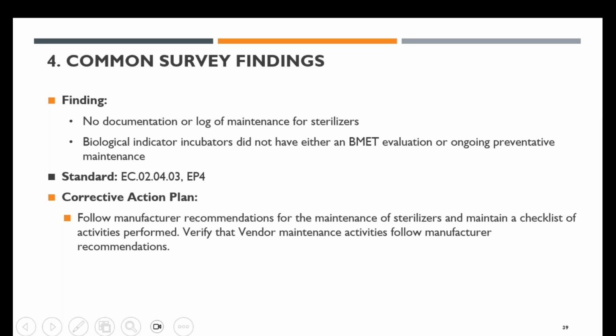A few things that we have done at some locations is sampling. You can go back and look at your service history on a quarterly basis and randomly pick some of the high-risk equipment, sterilizers, and see the type of documentation we have in place and who is doing that work order. If someone is doing it in-house, make sure they are complying with the manufacturer requirements, checklist, and parameters in the manufacturer recommendation. If it is under a contract with a service provider, make sure the documentation is intact within the system. Those are highly recommended on sterilizers.